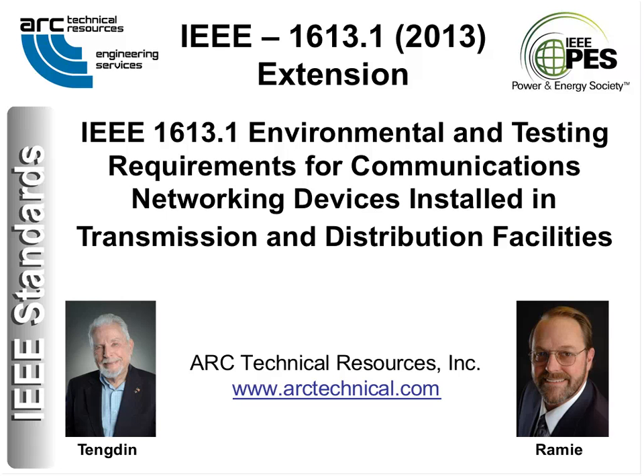My suggestion is that you run the IEEE 1613 and 1613.1 pair, and then you can do the IEC tests you just passed, because they're all the same. The levels may be even slightly less, but their criteria is identical. So you can get all your testing done at the same time, and you have a consistent burden.